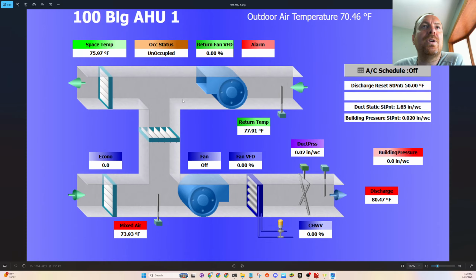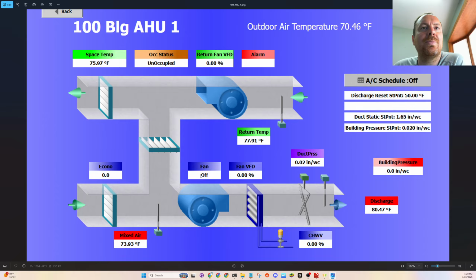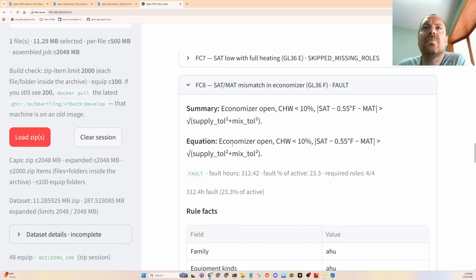I think I need to write this a little bit better. It's not shown here, but when this damper is open beyond its minimum position for ventilation, that's when we're just saying the economizer is open. I think it's just defaulted to like 40% or something like that. Economizer is open and chilled water valve is less than 10%. So that means that we're just free cooling.